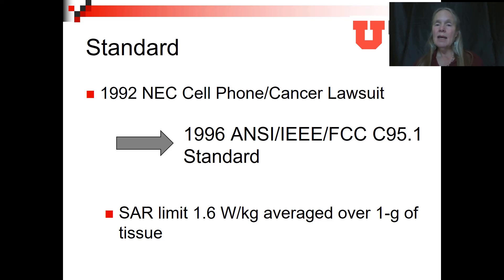This standard said that in the United States, the SAR limit of 1.6 watts per kilogram averaged over 1 gram of tissue was the maximum allowable SAR. In Europe, this is the CENELEC guideline, and it is 2 watts per kilogram averaged over 10 grams.